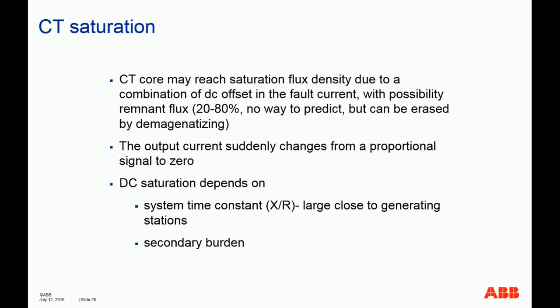DC saturation depends heavily on the system time constant, X over R. This X over R, for example, is very large closer to the generator. So that's why, when you are designing the generator protection and calculating the settings for the generator differential relay, you need to watch out for this X over R impact on CT saturation, because you will see a very big value for this X over R. So when you specify a CT for generator protection purposes, you need to watch out for that.